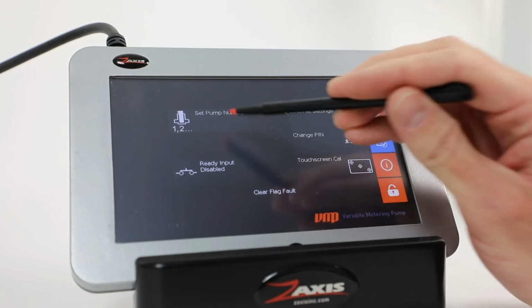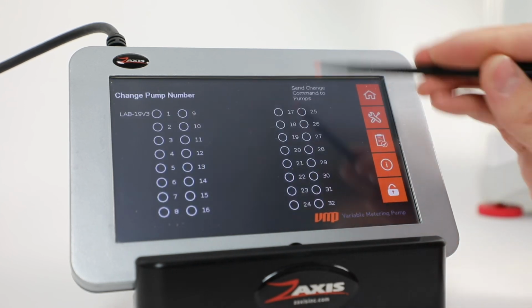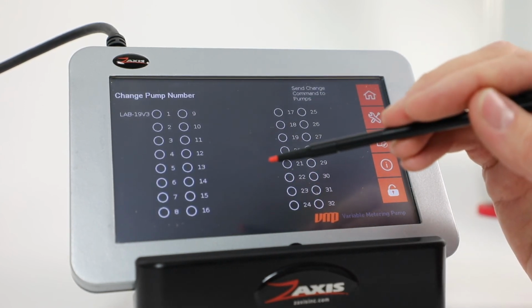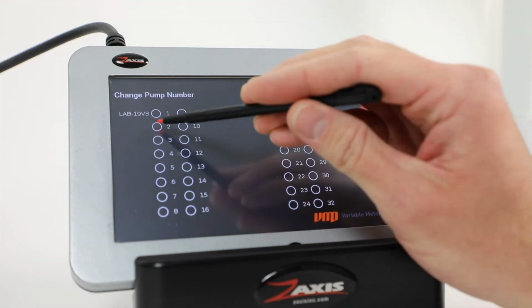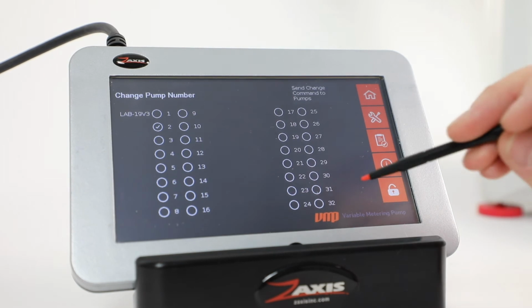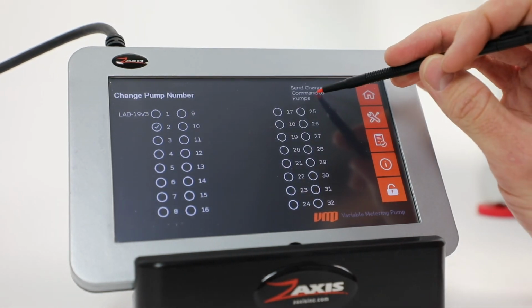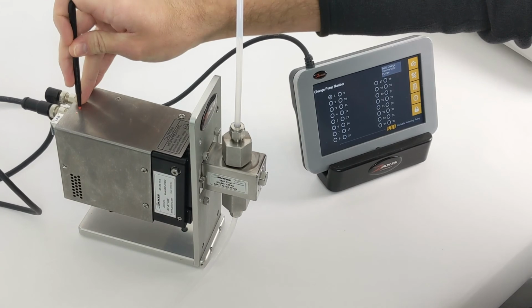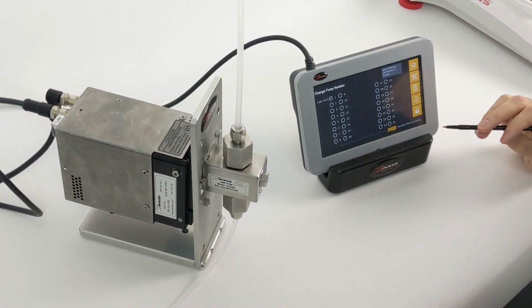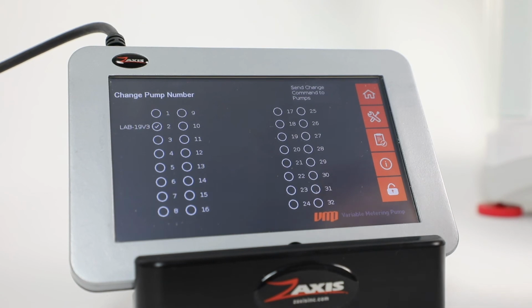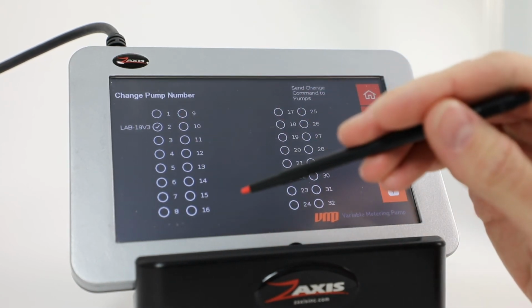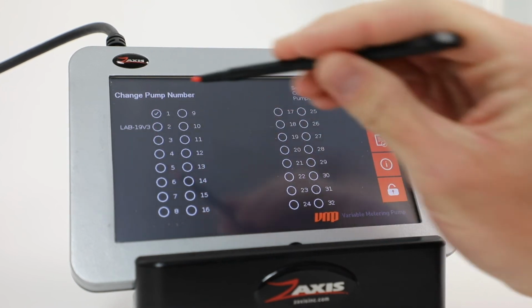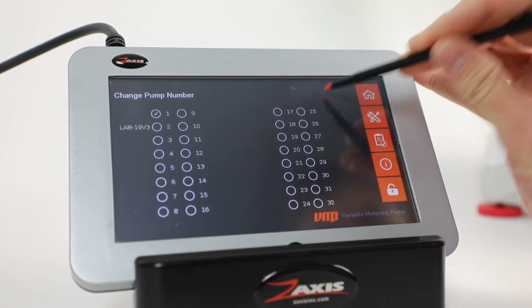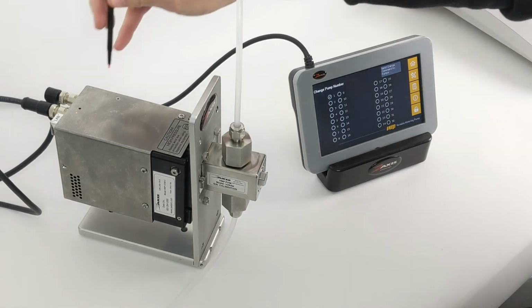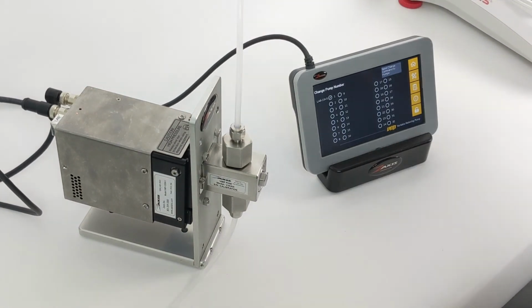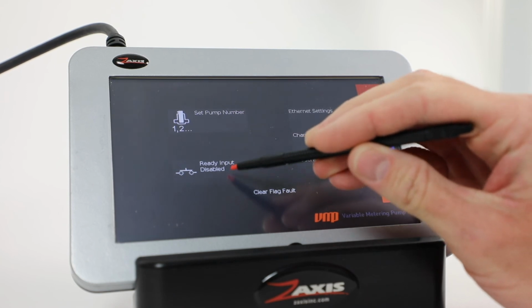Over here we have the set pump number. If we click that, you'll see that pump number screen pop back up. You want to change the pump number from say 1 to 2. Click 2 there, and then hit the send command button. And then on the back of the pump, there's a tiny little button next to the red LED. If you click that, it will populate the pump into pump number 2. And then if you want to set it back to pump number 1, click 1, click the send command button, and press that little button again. Now back to the checklist menu.